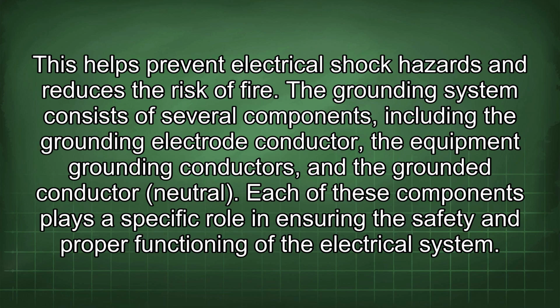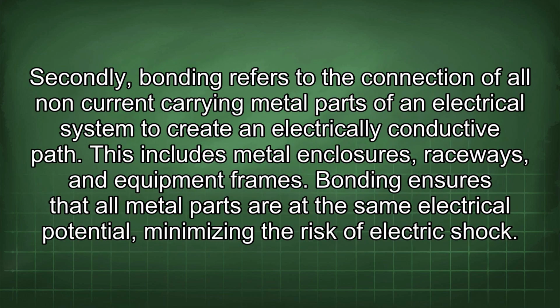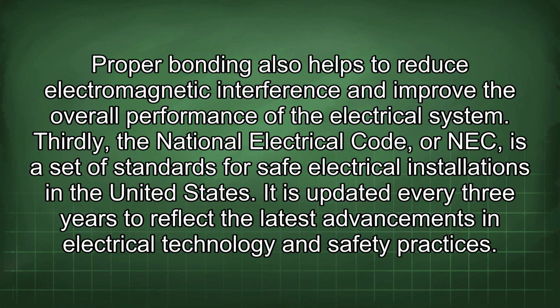The grounding system consists of several components, including the grounding electrode conductor, the equipment grounding conductors, and the grounded conductor (neutral). Each of these components plays a specific role in ensuring the safety and proper functioning of the electrical system. Secondly, bonding refers to the connection of all non-current carrying metal parts of an electrical system to create an electrically conductive path. This includes metal enclosures, raceways, and equipment frames. Bonding ensures that all metal parts are at the same electrical potential, minimizing the risk of electric shock. Proper bonding also helps to reduce electromagnetic interference and improve the overall performance of the electrical system.